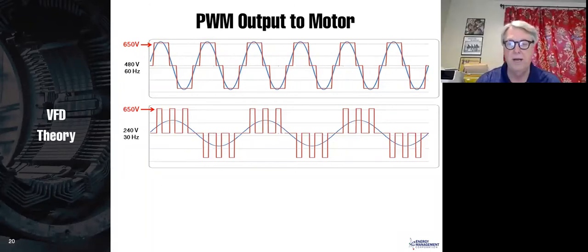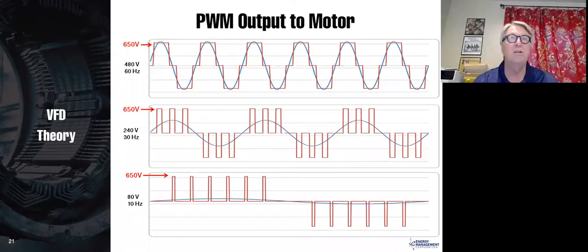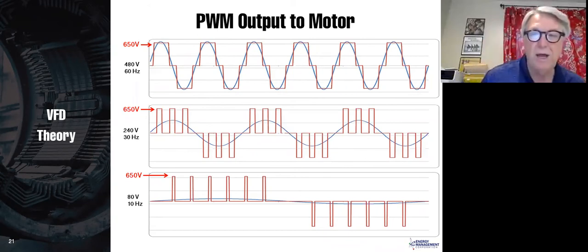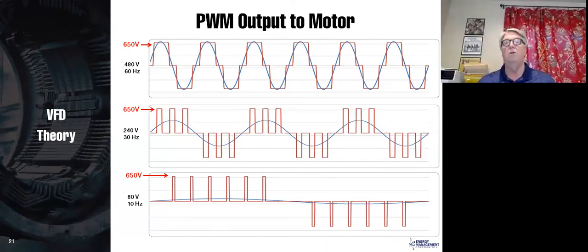Now, what if we want to go to 10 hertz? Well, if we go to 10 hertz, now that is 1/6 of 60. Therefore, the voltage has to be 1/6 of 480 volts. And now you will notice that the pulses need to be on only 1/6 of the time and off 5/6 of the time. And if we do that, we have an effective voltage of 80 volts. Notice here that the blue waveforms are simply AC sine waves of that voltage and that frequency. I put them in there just for your reference, but you don't get that out of the drive. What you get out of the drive is what we call this picket fence effect.